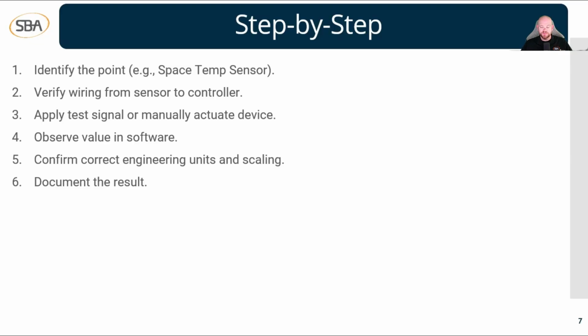So step 3 here is to apply our test signal so we can verify our wiring and everything's working good. And then step 4 here is to observe the value in the software. So we're going to our front end, our workstation, and we're going to pull up this point, and we're going to see if our value matches what we should be getting from our room. And you can also do this with a handheld thermometer. If you walk in the room, set it by the thermostat or by the sensor, you should get a pretty close reading to what the room's reading, and then you can go back to the computer, to your workstation, the software, and verify that you're getting close to the right reading. So that's step 4. We're observing the value in the software.